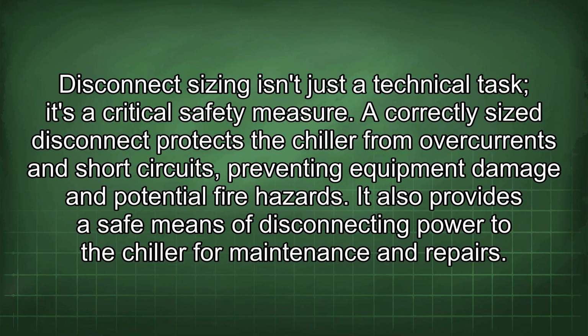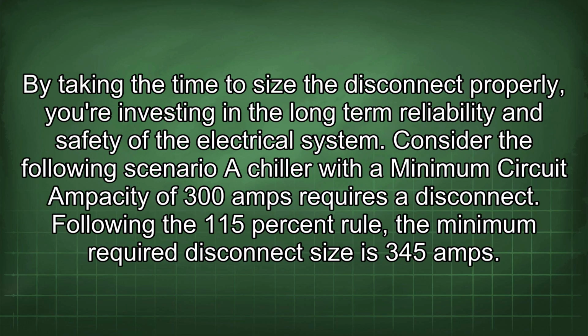A correctly sized disconnect protects the chiller from overcurrents and short circuits, preventing equipment damage and potential fire hazards. It also provides a safe means of disconnecting power to the chiller for maintenance and repairs. By taking the time to size the disconnect properly, you're investing in the long-term reliability and safety of the electrical system. Consider the following scenario: a chiller with a minimum circuit ampacity of 300 amps requires a disconnect.